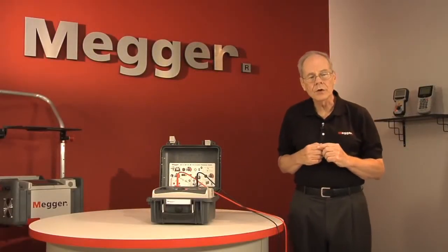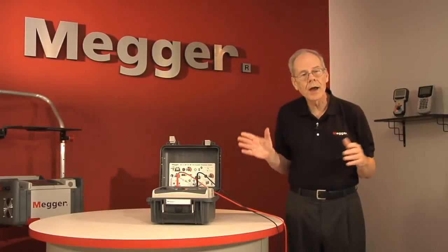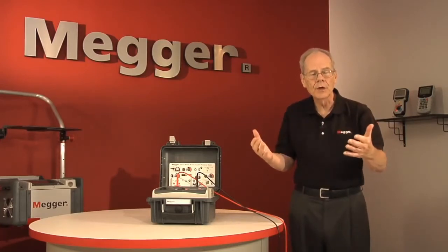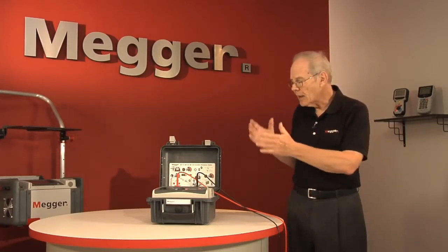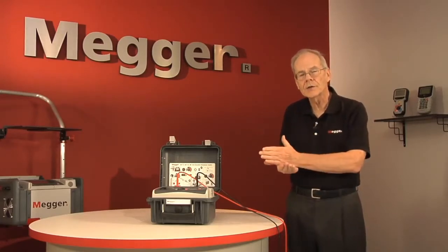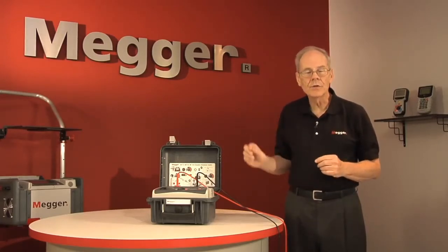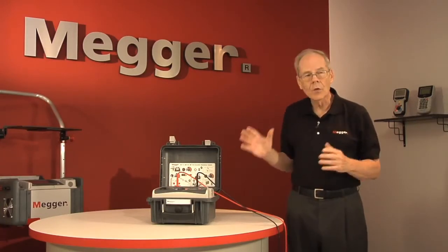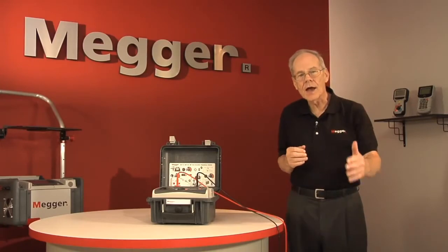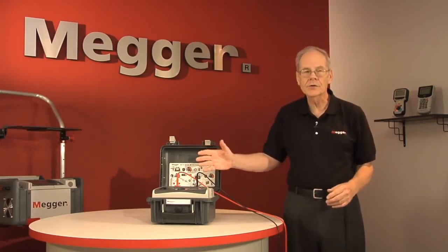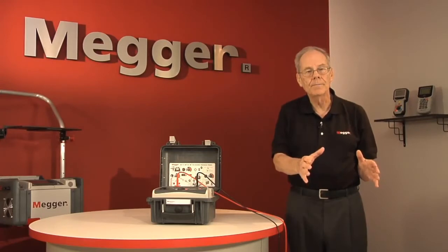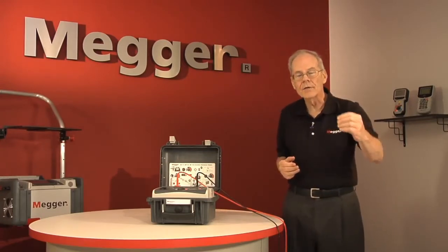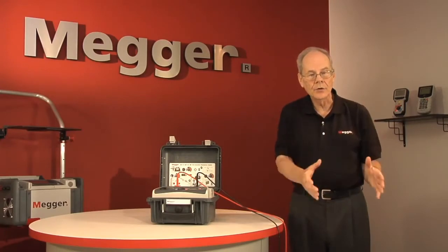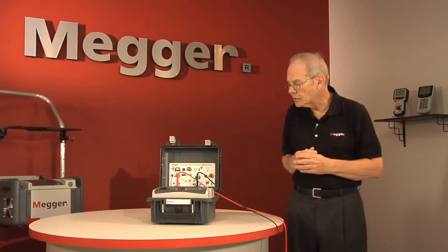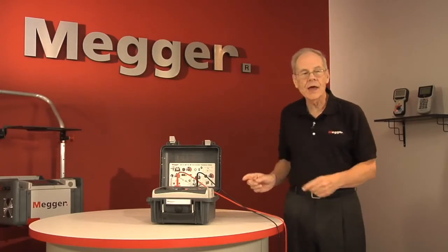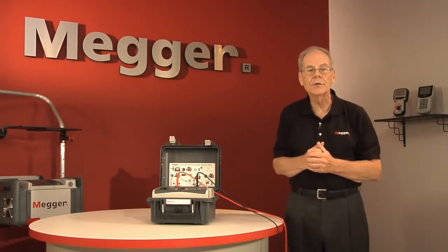Now, in all the tests that we've looked at so far, the tester has applied an active voltage and it's pulled leakage current and measured it. At the end of any of those tests that we've looked at so far, when the test voltage ceases, the tester automatically discharges the static voltage on the test item. Now, in all the other tests, this is a safety function, so that there is no static voltage left on the test item that could injure someone that came in contact with the test item. And the tester discharges that and monitors it, and you can watch that on the display.